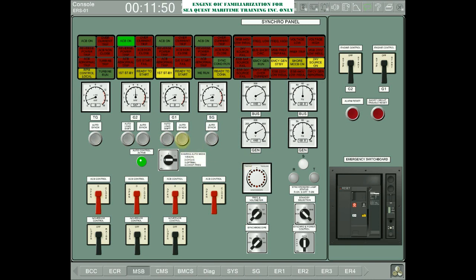In some scenarios it could be G2. So in this familiarization I'm using G1. And then press the synchro button. Oh, by the way, this synchronization lamp should also be placed to G1. No, it should be on manual so that the auto synchro button will light up. And then the synchro and power control should be on auto. Okay, let's press auto sync. See, it will become white, and then let's wait for number 1 GE takes some of the load from number 2. Okay, now they are on synchronized condition.